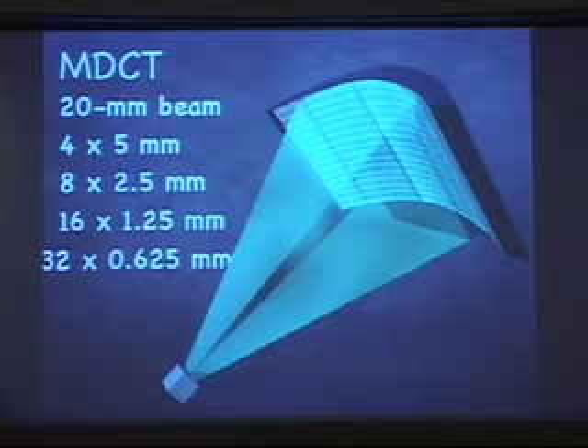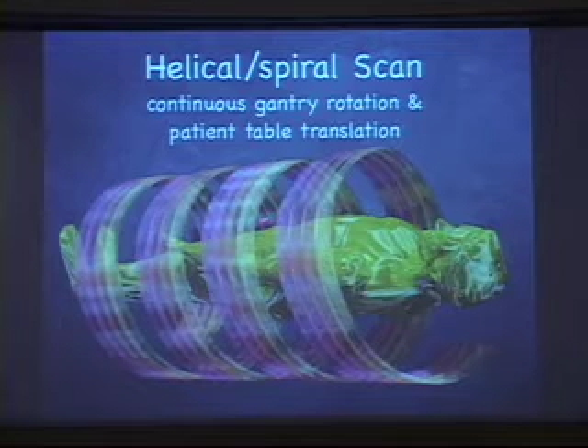And so for those of you who are clinicians who work with imagers and you are not seeing image quality like I'm showing you here today, it's important to interact with your imagers to be sure that they are taking advantage of the data and not just averaging individual sections to get you thicker sections, which is often what happens. This geometry is established to couple with a simultaneous table translation while the gantry rotates so that we get what's called a helical or a spiral path, so-called helical or spiral CT. This is a schematic of 4 rows, and this is basically how our CT angiography works at this time.